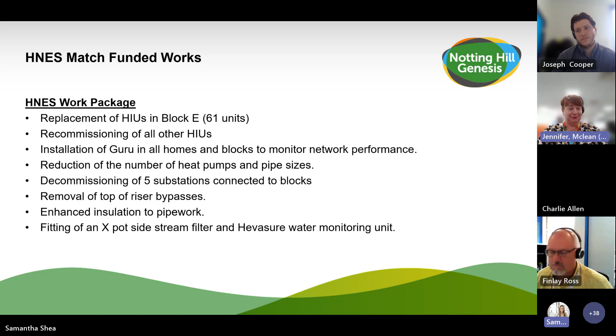And we've got a picture of that later. The other parts of the package was to remove the top of riser bypasses and enhance the insulation to the pipework to current regs, as well as fitting an X-Pot side stream filter and Hevasure water monitoring unit.